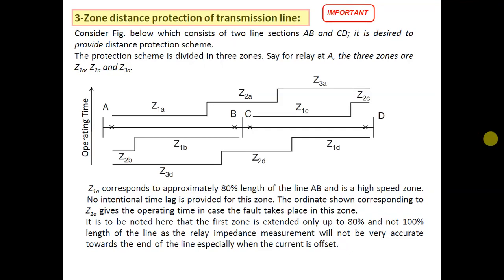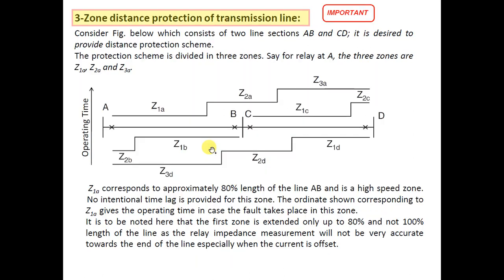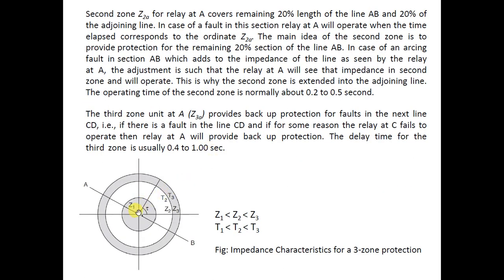Today we are going to discuss about three-zone distance protection of transmission lines. In the previous class we discussed about distance protection, but one disadvantage with conventional distance protection is that it will not be able to protect 100% length of the line, because due to inaccuracies in relay elements and instrument transformers, the relay might not distinguish between 99% and 101% of the line length, leaving some portion unprotected. This difficulty can be eliminated by three-zone distance protection, where every point on the line is protected by three layers of protection.